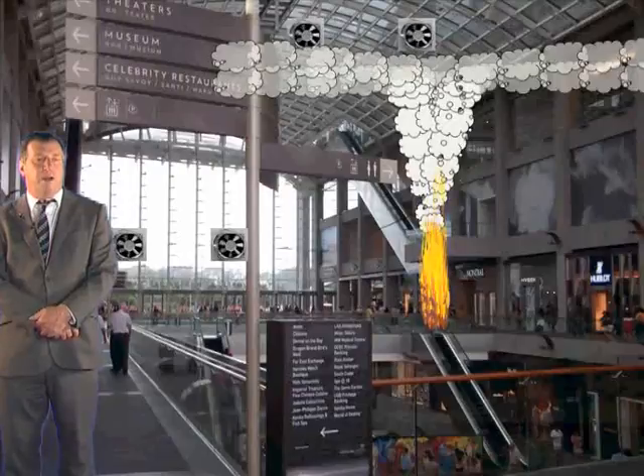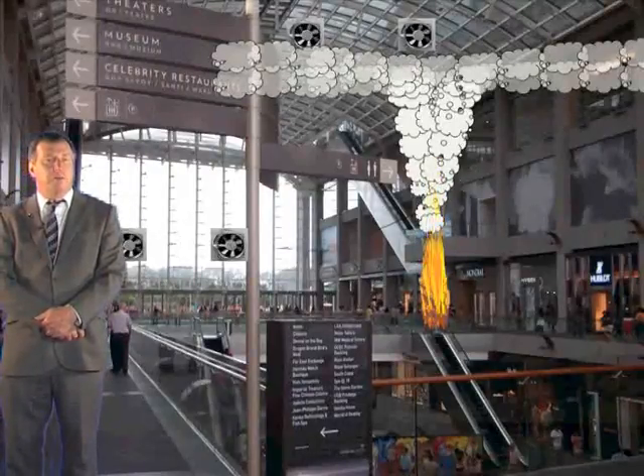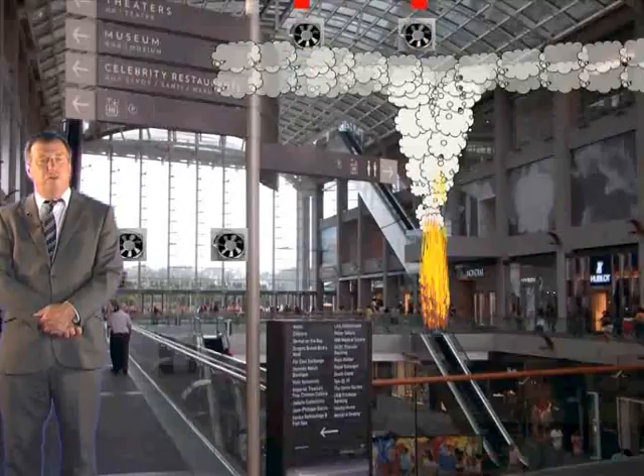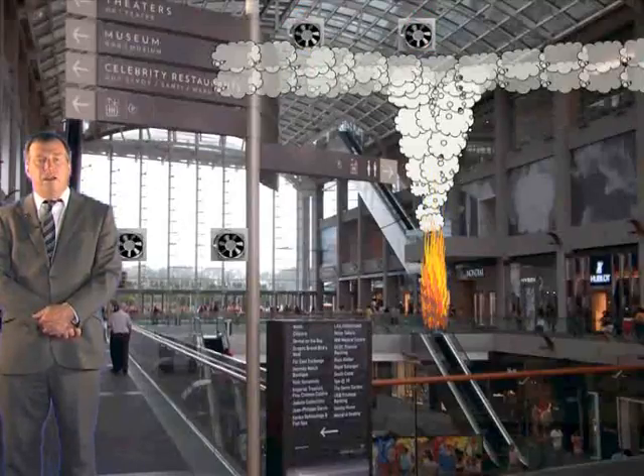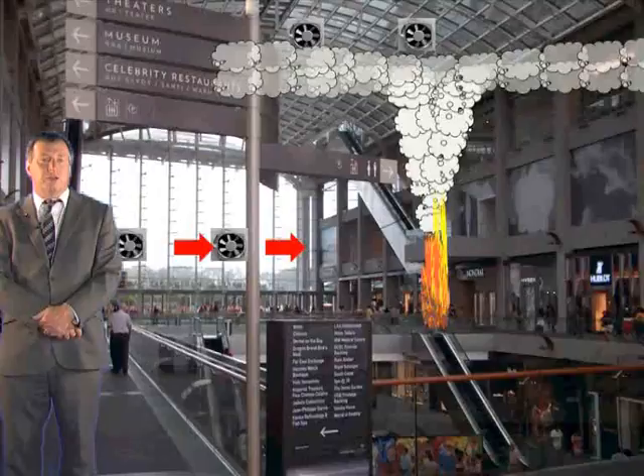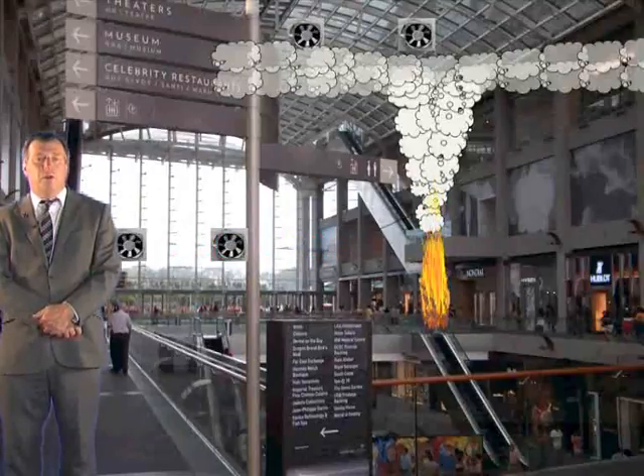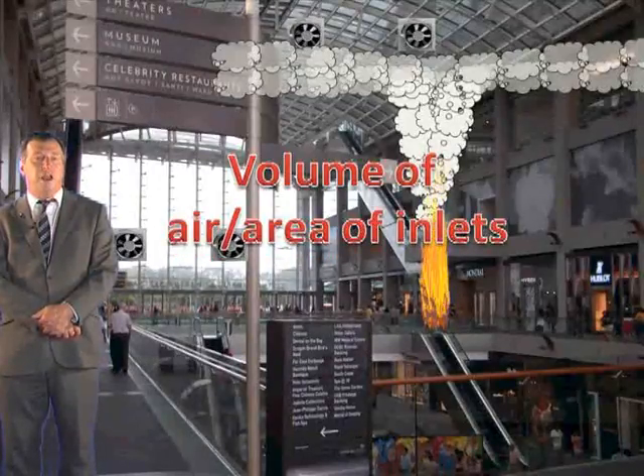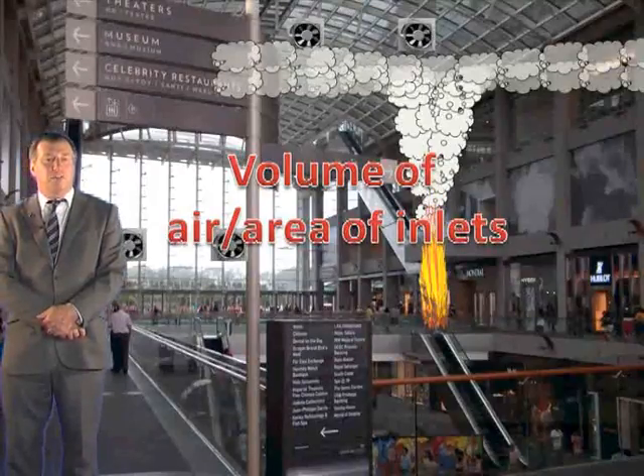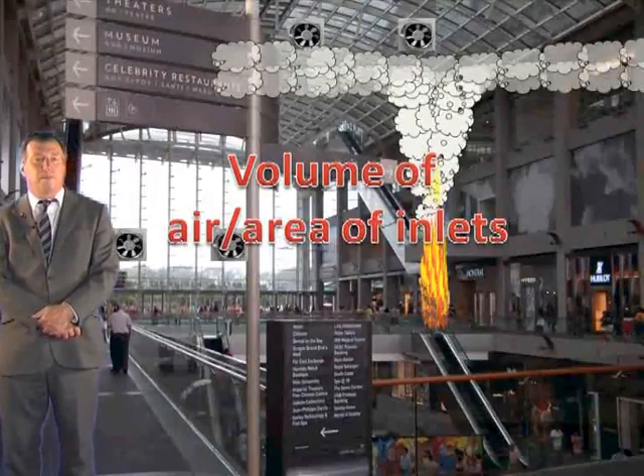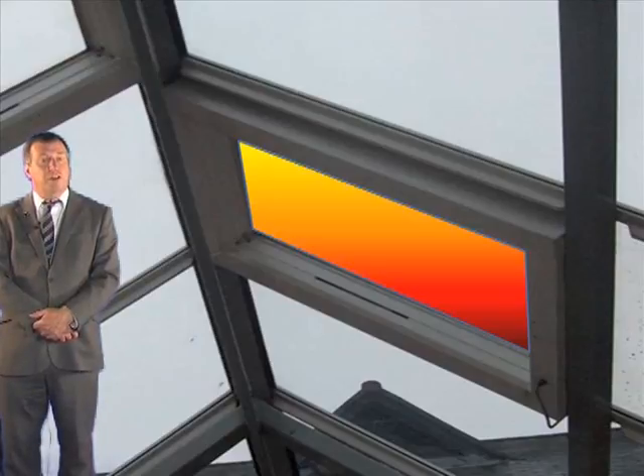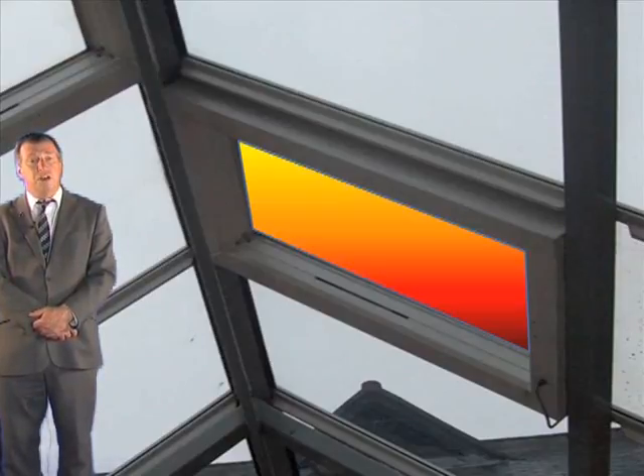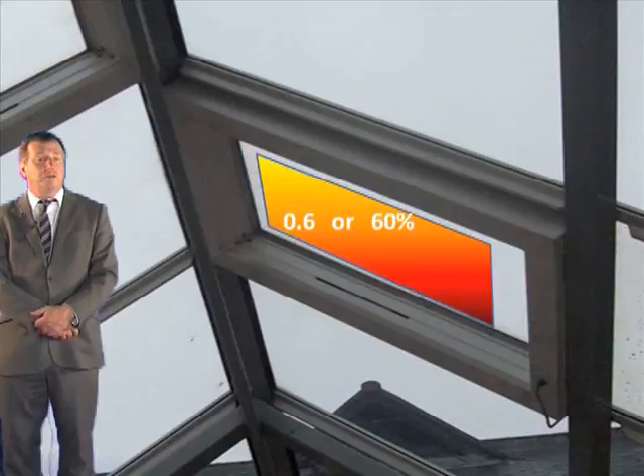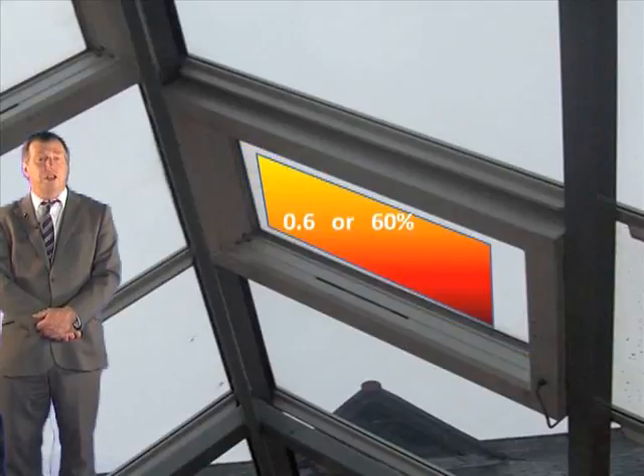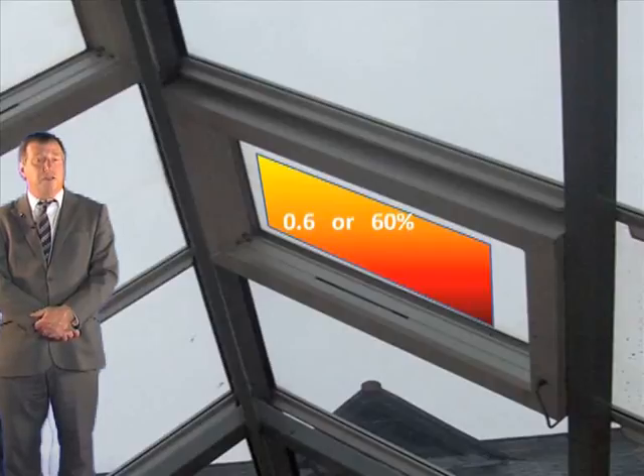Returning then to the powered systems, we know how much smoke is being extracted from the building, and it's a fair assumption to suppose that the same amount of air is going to be drawn into the building through the openings to the outside. If we divide the volume of air that is entering each second by the area of the inlets, then we get the velocity that the air is coming in through those inlets at. Remember from the section on natural ventilation that vents are not 100% efficient, and we assume the default value of 0.6 or 60% for the coefficient of inlet. This applies even if the vents that are being used are doorways.